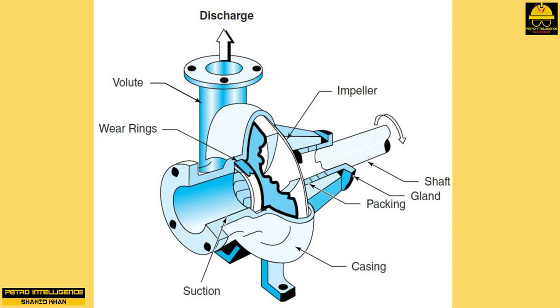Mechanical seals require very low maintenance, have a reasonably long life, and have very little product leakage. The stuffing box and packing gland hold packing firmly against the shaft and casing. A slight bit of internal leakage keeps the packing lubricated and cool. The packing material, located between the casing and the shaft, consists of rings composed of flexible material coated in graphite or Teflon. The packing needs to be replaced frequently.